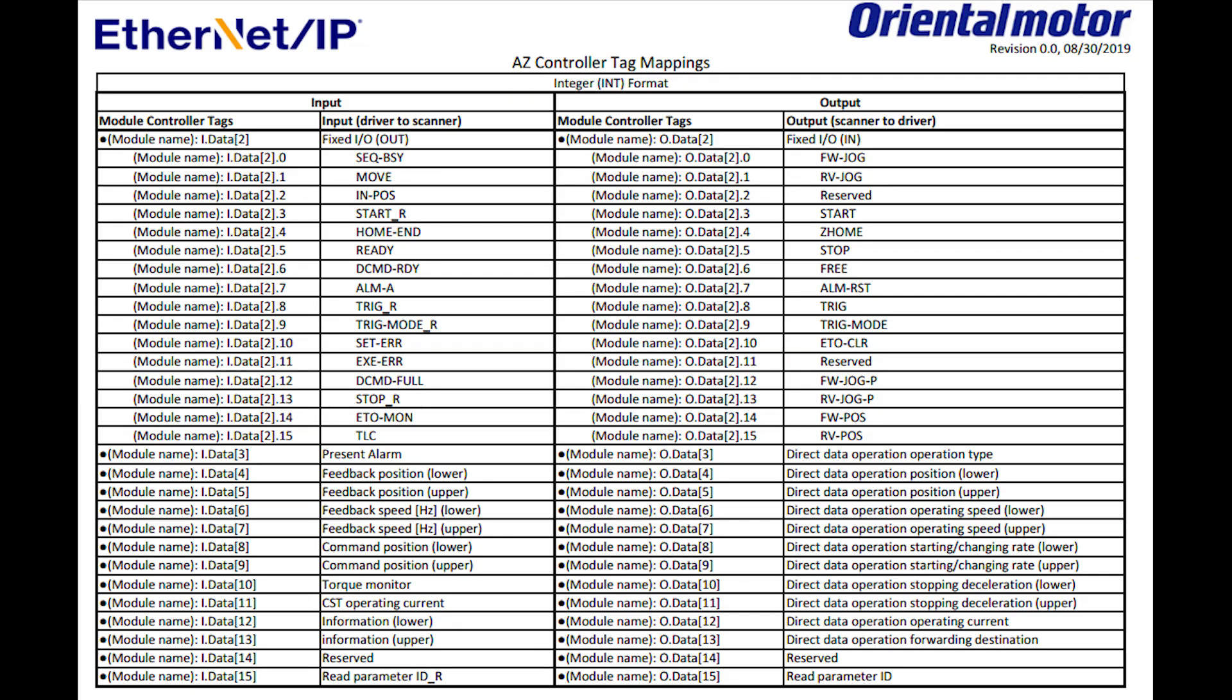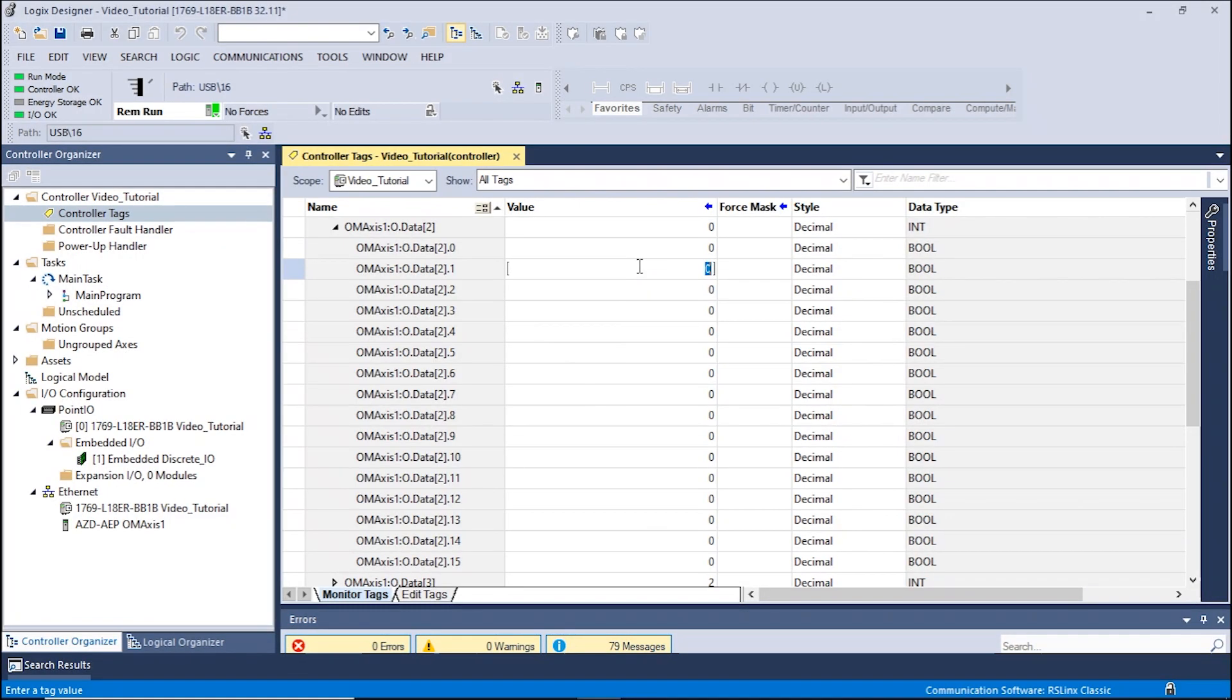Now let's try moving the motor in the opposite direction. In the controller tag mapping, we see a reverse jog located under the output data 2 bit 1. Enter 1 into data 2 bit 1. The motor will now move in the reverse direction. To stop the motor, enter a 0 value.